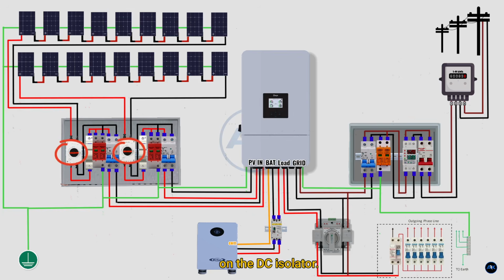Turn on the DC isolator, followed by the DC breakers inside the combiner box. The inverter should begin detecting the solar voltage on each MPPT channel. If the readings are consistent with your calculated open circuit values, the PV side is ready to operate. Now it's time to energize the AC side.